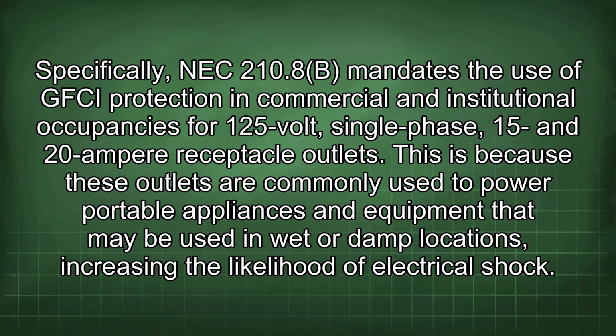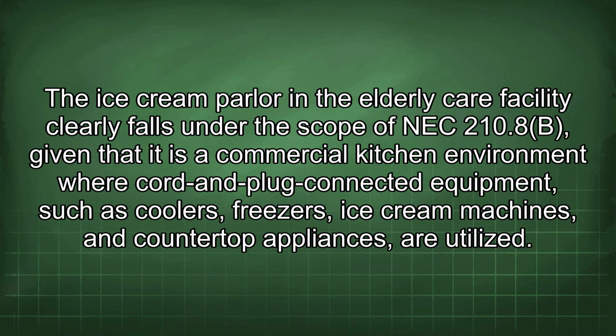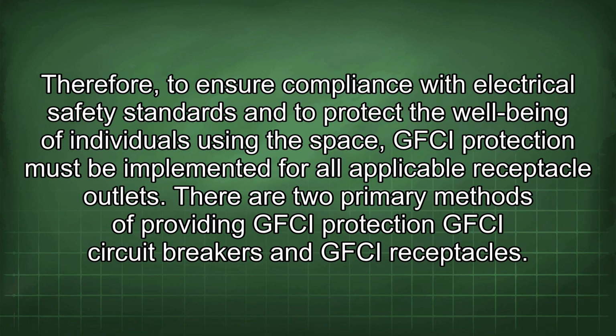This is because these outlets are commonly used to power portable appliances and equipment that may be used in wet or damp locations, increasing the likelihood of electrical shock. The ice cream parlor in the elderly care facility clearly falls under the scope of NEC 210.8b, given that it is a commercial kitchen environment where cord and plug-connected equipment such as coolers, freezers, ice cream machines, and countertop appliances are utilized. Therefore, to ensure compliance with the electrical safety standards and to protect the well-being of individuals using the space, GFCI protection must be implemented for all applicable receptacle outlets.